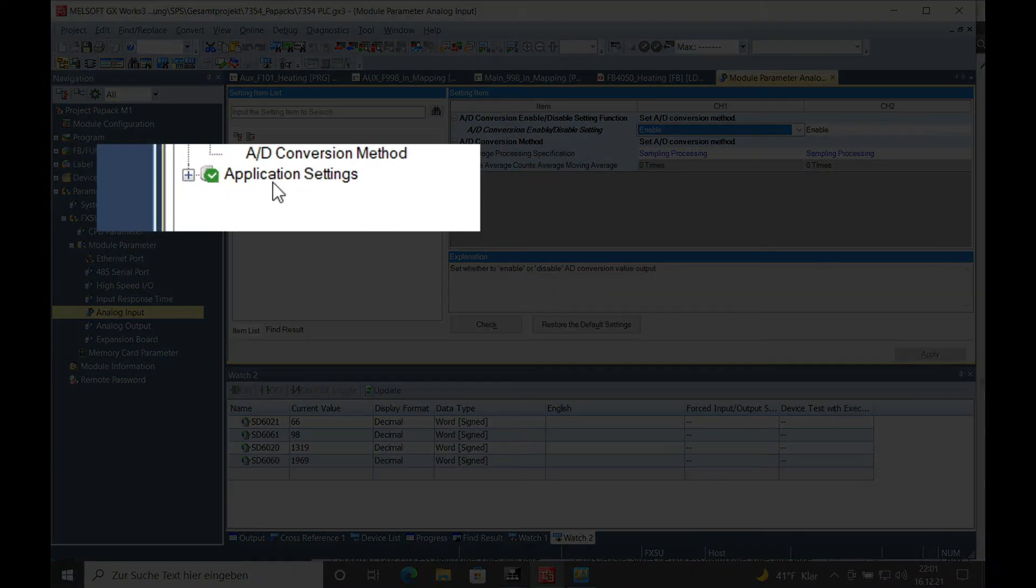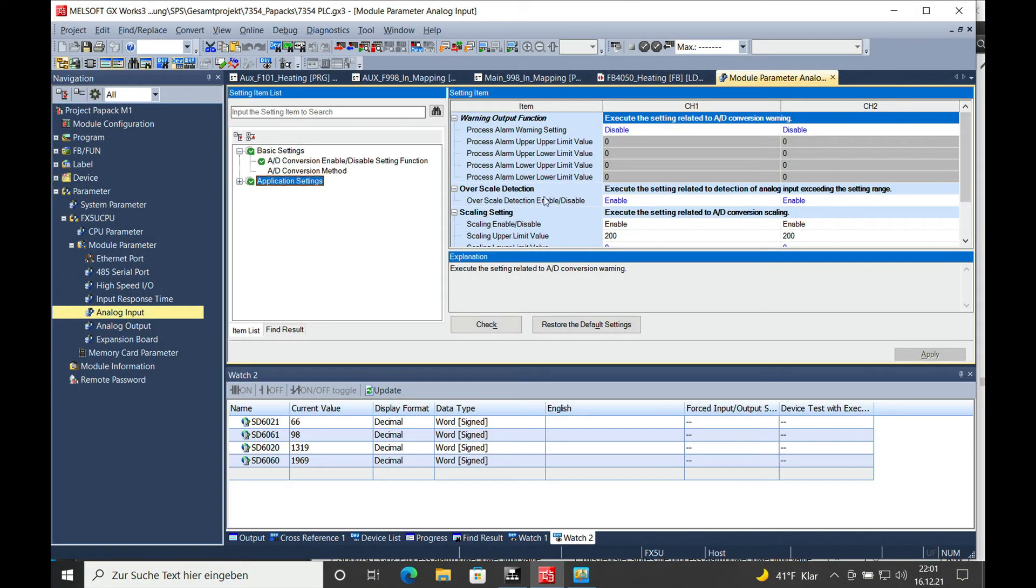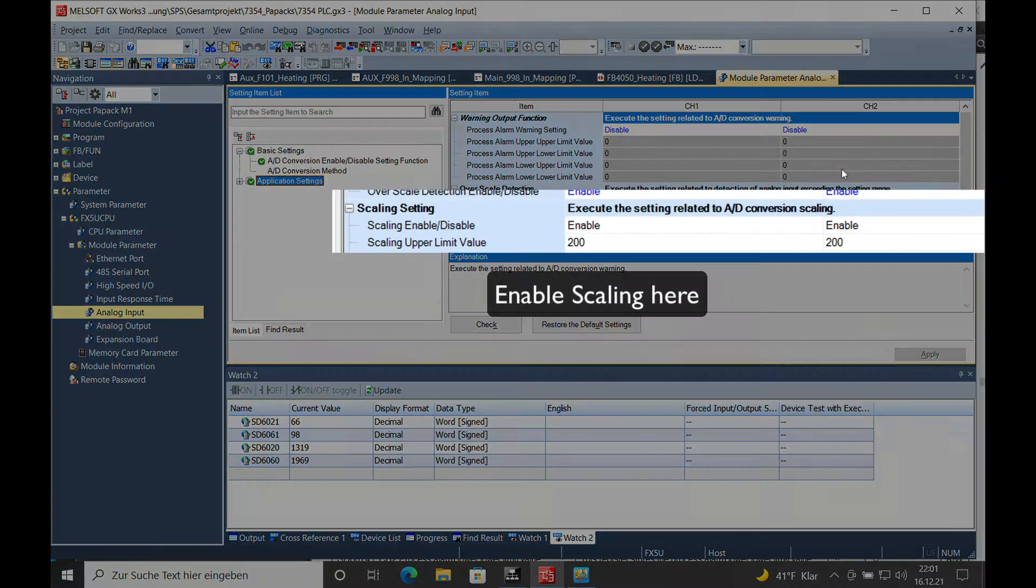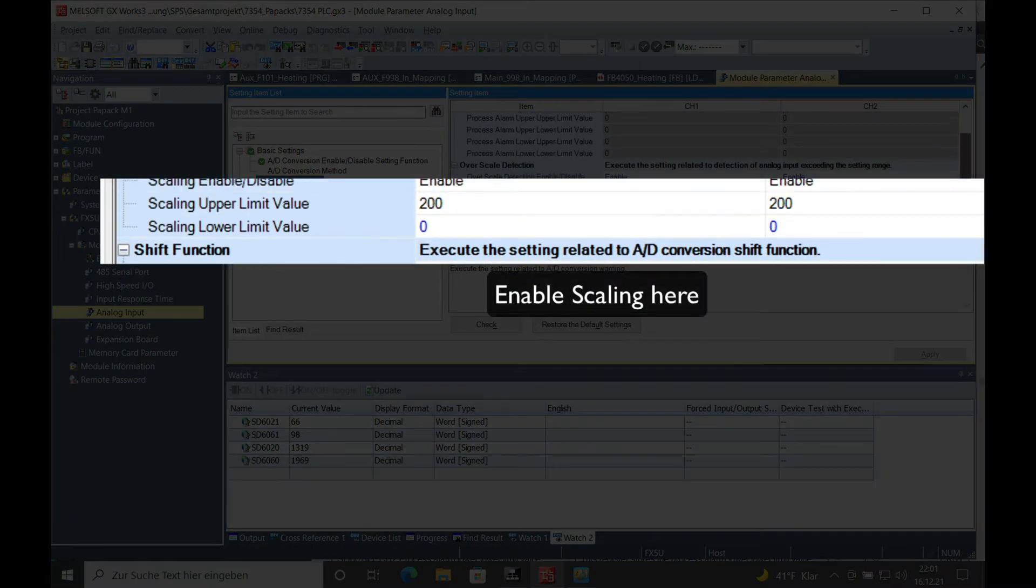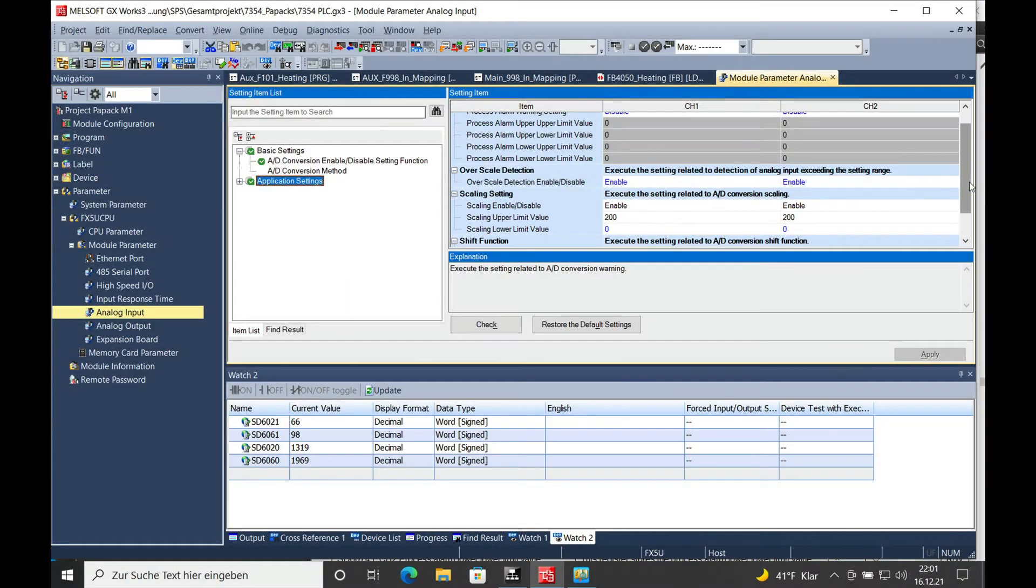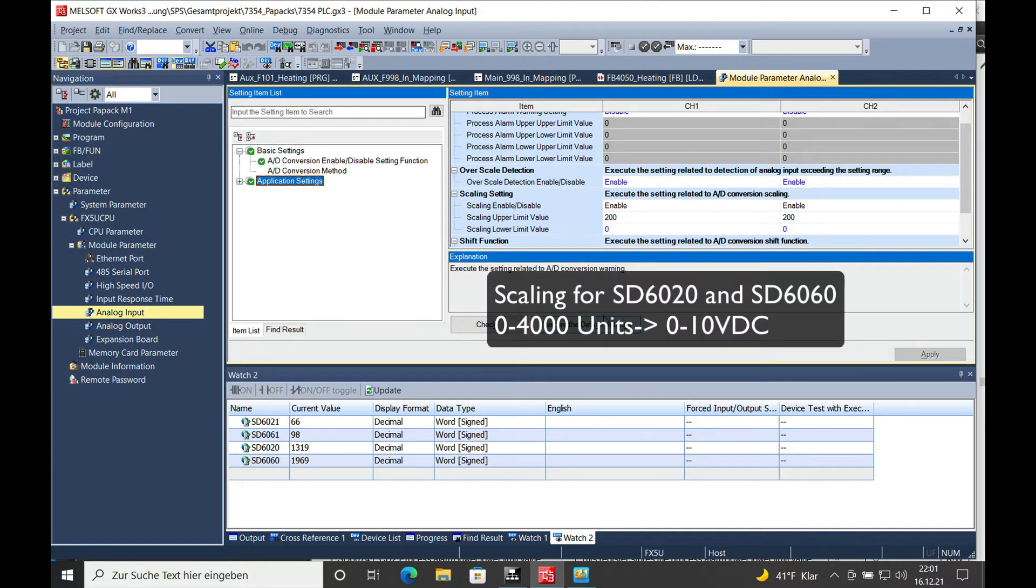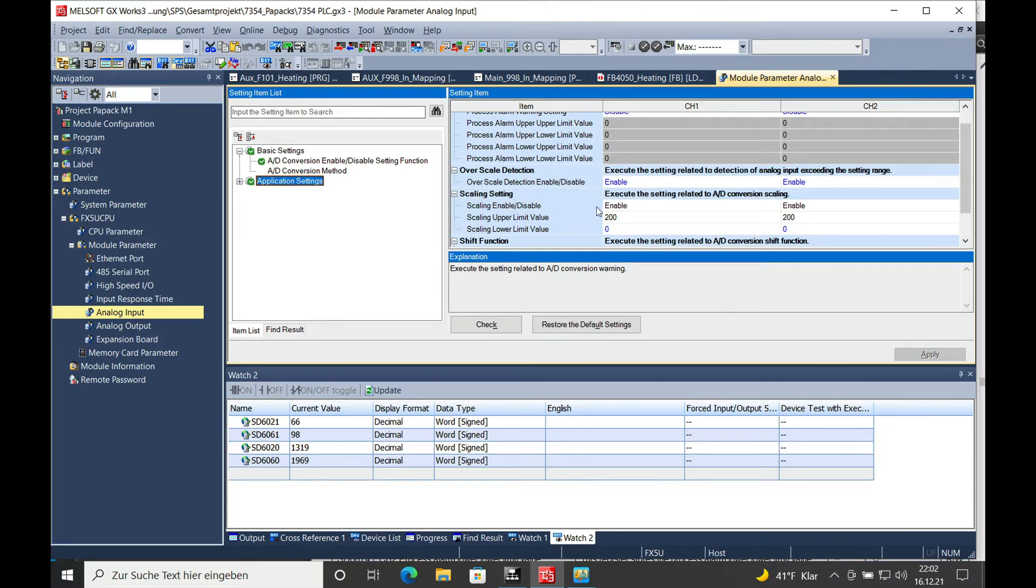In the application settings you will actually see whether you can scale the value. The value that is read in on the SD6020 is from 0 to 4000 units based on 0 to 10 volts DC. If you don't want to calculate this in your program, you can set the scaling right here.